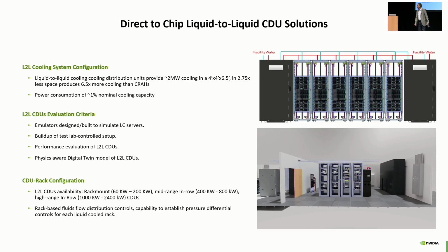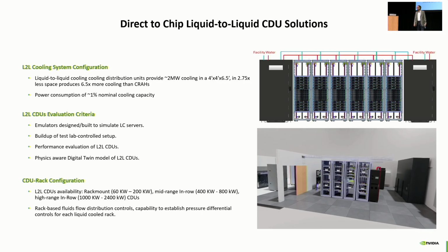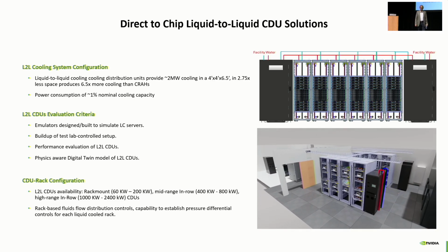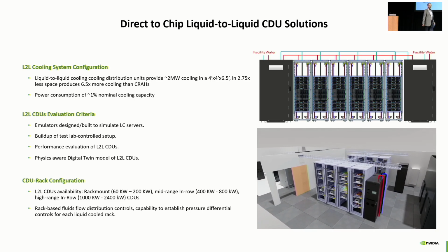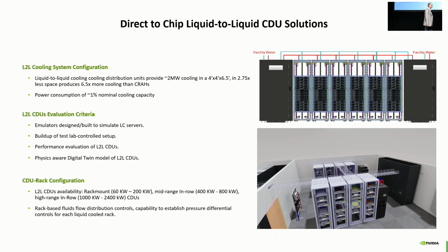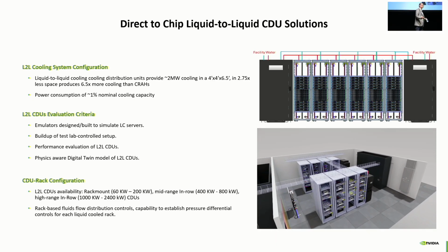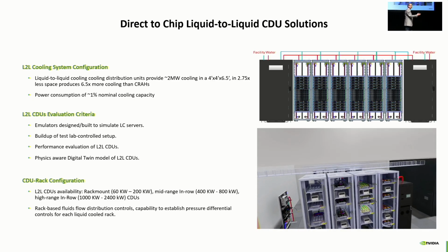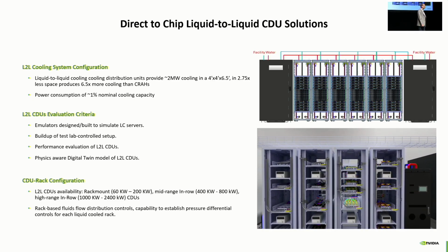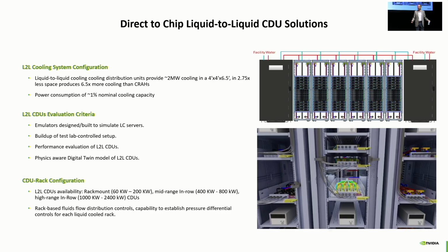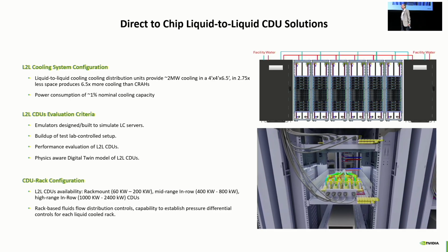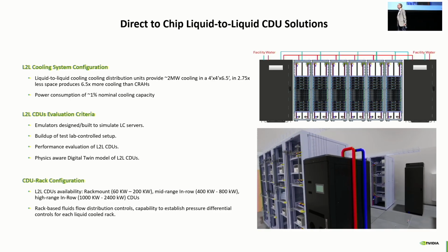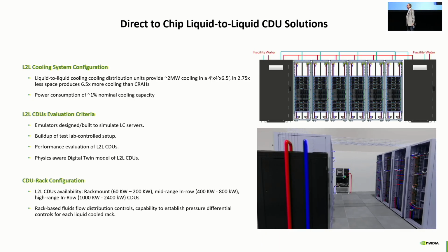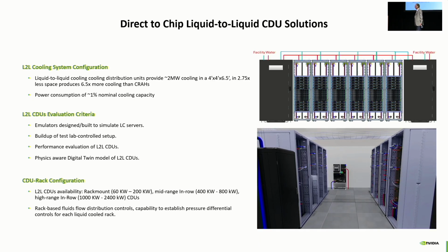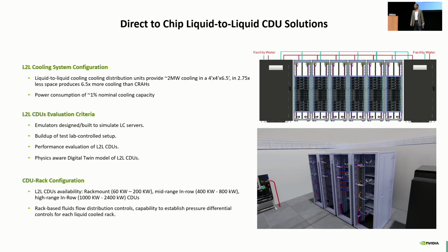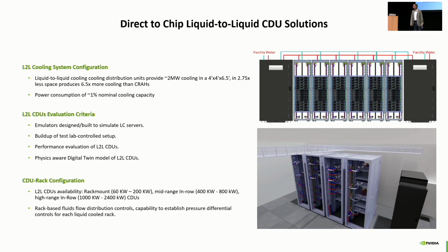We go to liquid, same phenomena in our labs. We create this digital twin phenomena in our labs, and I'm going to walk you through that. Large CDUs, liquid-to-liquid CDUs, multiple racks, emulating heat load with heat load emulators with cold plates attached to them, removing heat surgically from the source of the heat, like emulator heat sinks attached to the cooling distribution unit, pushing liquid out.